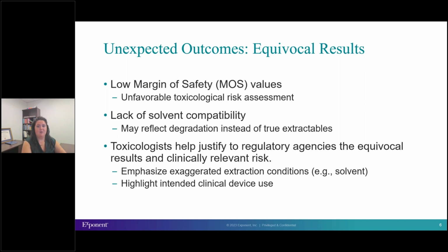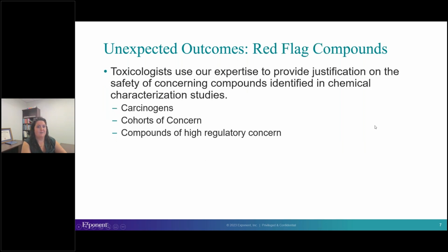We can also provide this rationale as justification for a lack of solvent compatibility and not actual toxicological risk from the device. It's also not uncommon for us to encounter red flag compounds, so things like carcinogens, cohort of concern members, and compounds of high regulatory concern in the device extracts. And we know when we get these red flag compounds that it can be unsettling for clients.